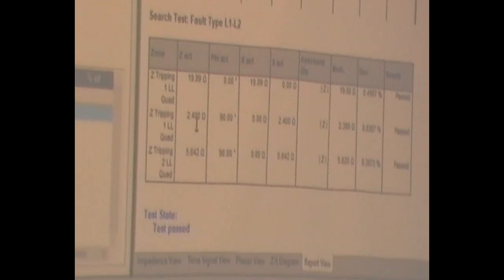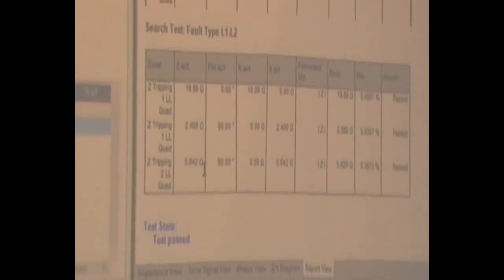Again, you're comparing with your setting. You already recorded the setting. You only take from here the actual measurement, which is the actual relay characteristic. For the phase, it's supposed to work in 19.8. It worked in 19.8. And the reactance is basically the same, but again, you have a little bit different result: 2.4 for zone 1 and 5.64 for zone 2.